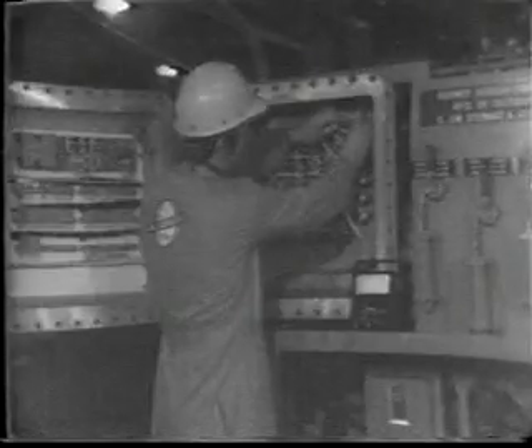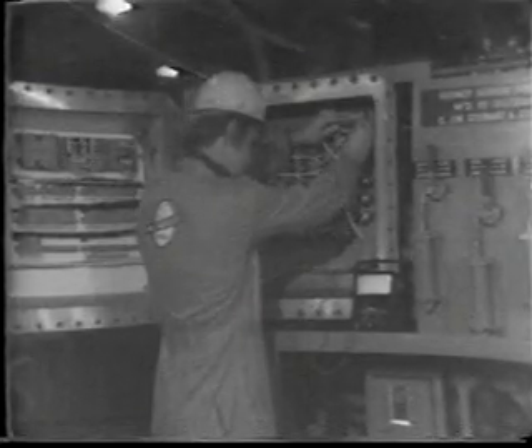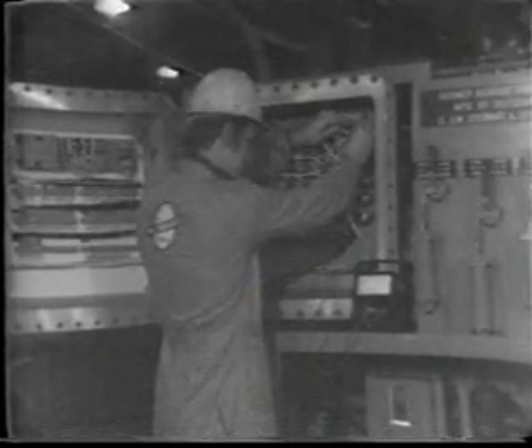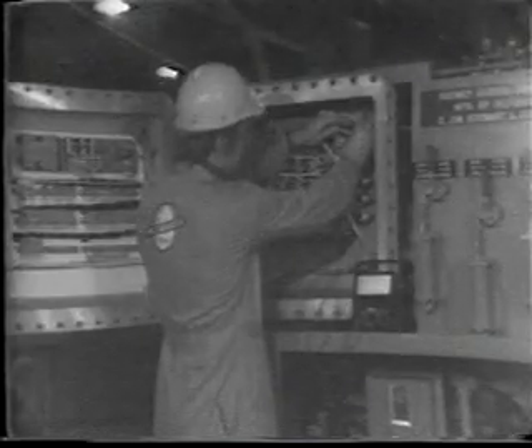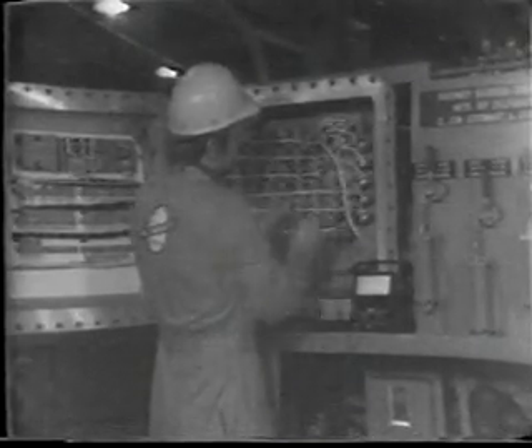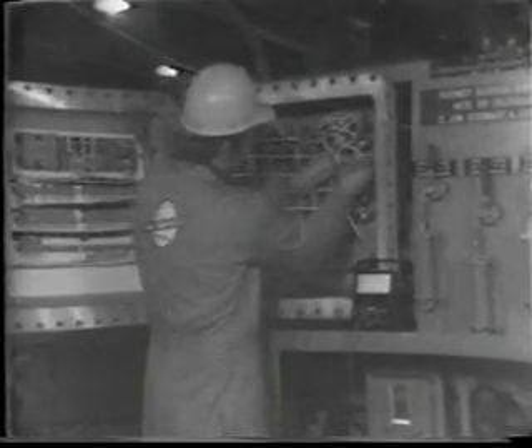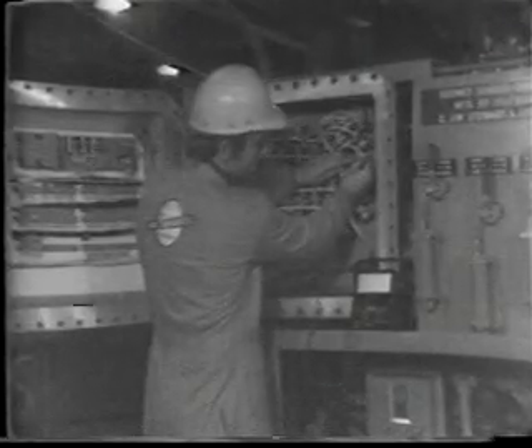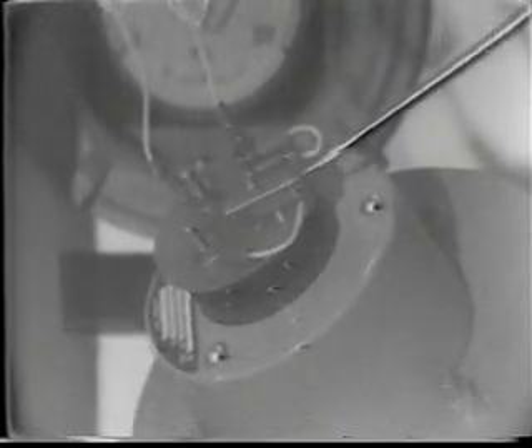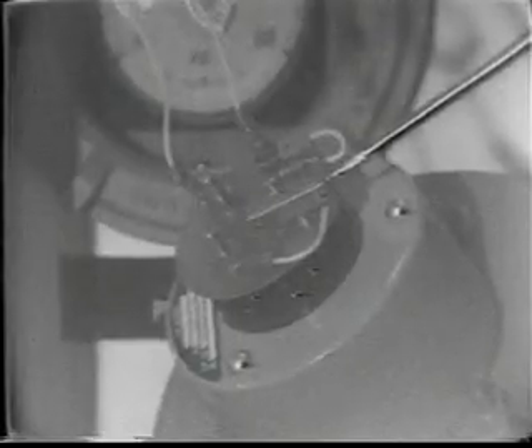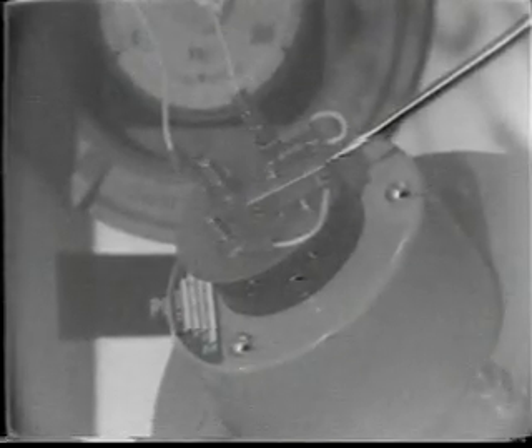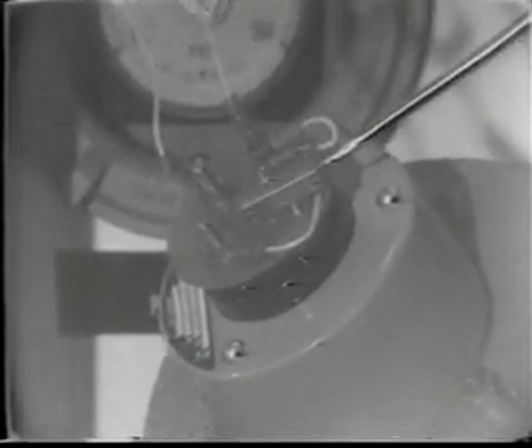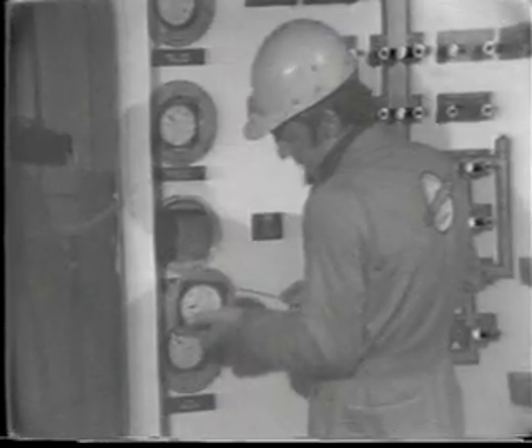If just one meter is reading incorrectly, consult the schematic and check the voltage on the input and output side of the pressure transducer for that circuit. If there is voltage on this circuit, calibrate the meter by adjusting the trim pot on the meter calibration. If there is no voltage on the output side of the transducer, replace the transducer.